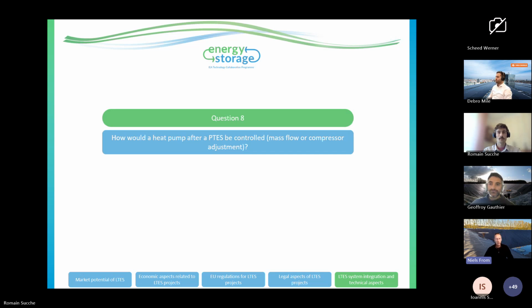The first example is when the heat pump is using an external heat source, it could be waste heat or ambient air, anything like that. In this case, the cold side of the heat pump is controlled as usual, so there's nothing special there. On the warm side, you could control the water flow to control the outlet temperature from the heat pump, because normally you want a fixed outlet temperature, and then the heat pump should control the water flow.